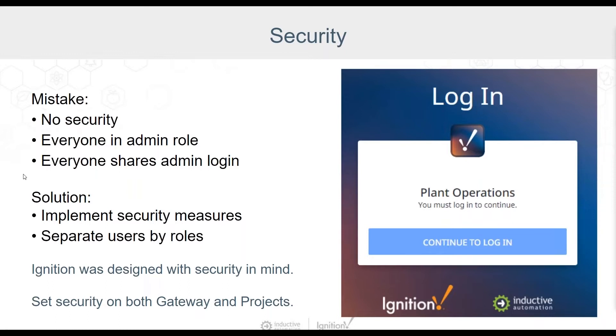Vision clients require a login by default, but can be configured with an auto-login. Perspective sessions are open by default. Before deploying your Perspective projects, consider requiring a login for the project. If you do allow open access, a guest user, or auto-login to launch a project, be sure to set restrictions on components inside the projects.